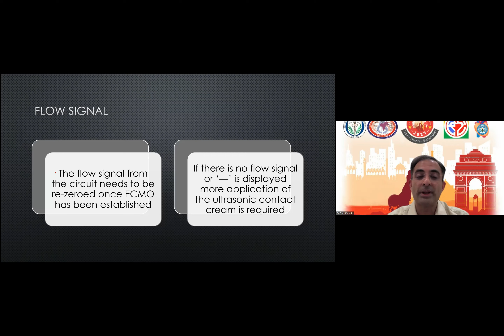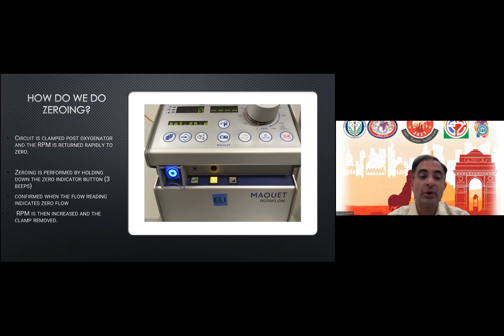The zeroing is done by clamping the circuit post oxygenator, as already mentioned, and we reduce the pump flow to 0 and press the zeroing button for about 3 seconds till the 3 beeps occur, and you find that the 0 comes on the flow reading, which indicates that the ECMO is ready to go.